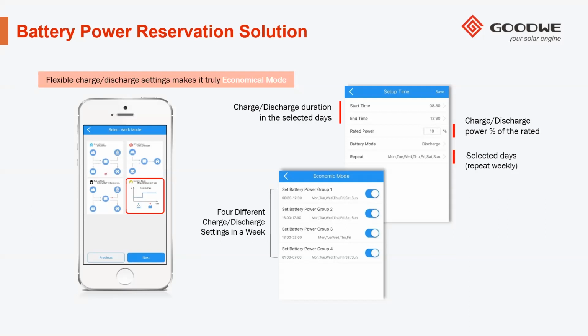But should you have the need to charge your batteries a bit faster or have a bit of flexibility in your system, you can use economical mode and adjust your rated charging power as you see fit. I normally wouldn't recommend more than 50% because you don't need to charge your batteries in under an hour. But it's all up to you. 50% is normally the recommended maximum that I would say. You'll see we have 4 different groups under economical mode, so you can set 4 different charge and discharge times. Please note that any time that is not set in this will then fall back to a default discharge time.